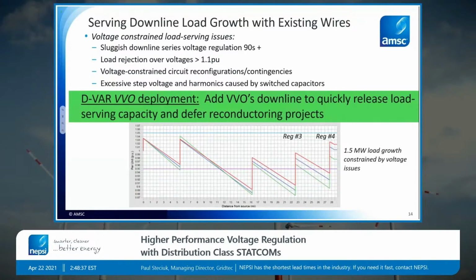So on the bottom graph here is a long feeder profile using line regulators. This was a utility that we were working with that was looking to serve an additional 1.5 megawatts of load. And we can see some of the challenges that pop up when that happens. Specifically, very discontinuous voltage profiles due to the line regulators. And other common issues include, for example, load rejections, which I covered.